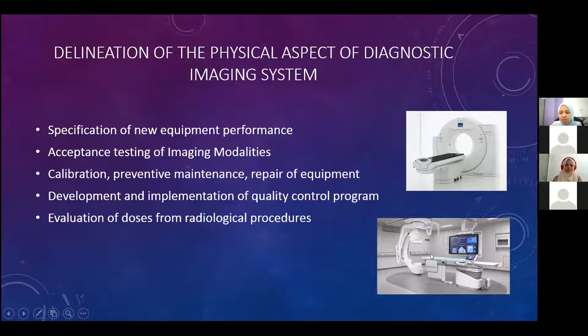The medical physicist plays an essential role in performing acceptance testing of imaging modalities before clinical use. Acceptance testing is important to ensure that newly acquired modalities are well within manufacturer's specifications and allow establishment of baseline measurements for future comparisons. So we use this baseline as a reference for our routine QC test later.